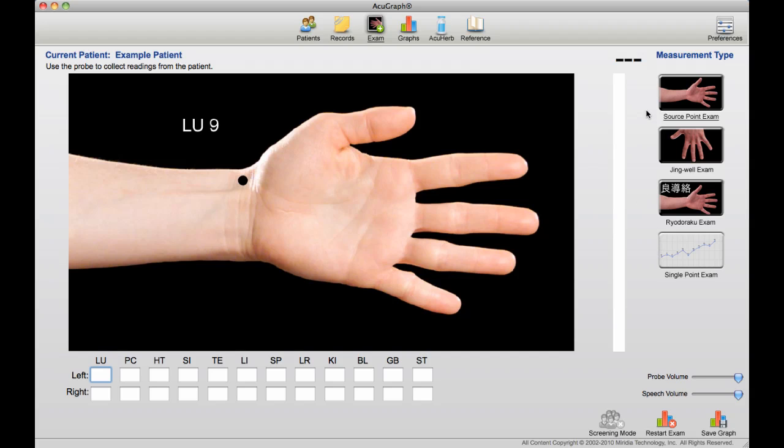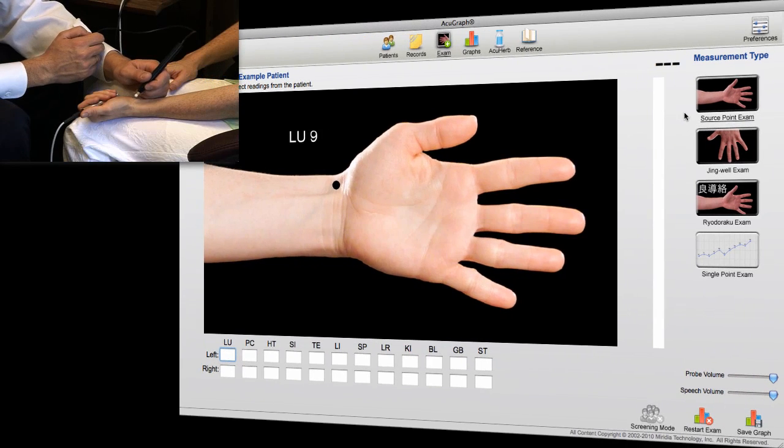This is a source point exam I have selected, so to perform the exam, simply use the probe to take the measurement at the point that's indicated in the illustration, and you'll get audio feedback to show you when you're on the point.